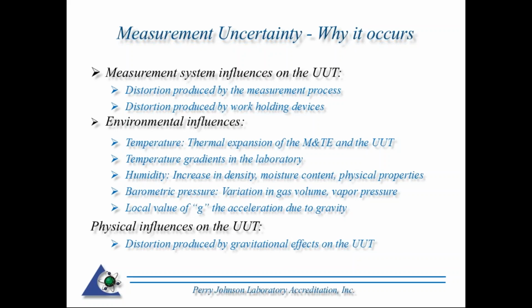Humidity, increase in density, moisture content, physical properties, barometric pressure, variation in gas volumes, vapor pressure may affect different types of calibration. In all three of those, temperature, humidity, barometric pressure, for anybody that's doing any calibration where you have to take air buoyancy into effect, each one of those is figured into that equation, and so you would have an uncertainty associated with each one of those.